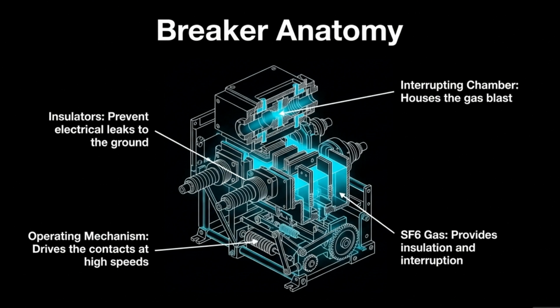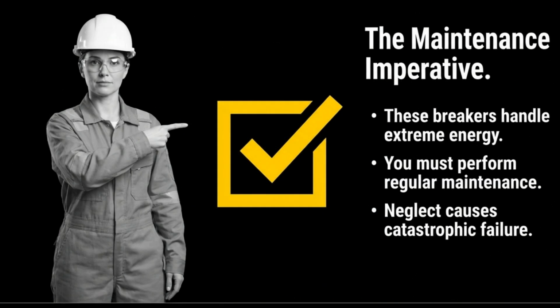The breaker anatomy includes the interrupting chamber for the gas blast, SF6 gas for insulation and interruption, insulators to prevent electrical leaks, and the operating mechanism to drive contacts at high speeds. Regular maintenance is crucial. These breakers handle extreme energy, and neglecting maintenance can lead to catastrophic failure.